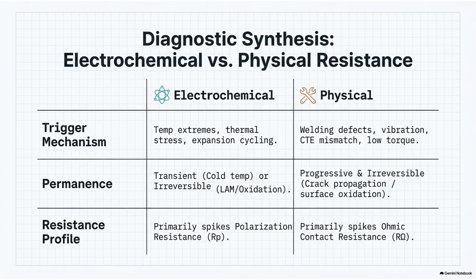Which introduces fretting wear and oxidation, right? Yes. Bare copper oxidizes very rapidly in the presence of humidity. And here's the critical electrical distinction we have to make. Copper oxide is a semiconductor bordering on being a total insulator. It blocks current. It is highly resistive. So as the bolt relaxes, a vibration causes microscopic rubbing, which we call fretting, between the bus bars. This fretting continually breaks off fresh copper particles, which immediately oxidize. Oh, so it just keeps building up more and more rust, basically. It builds up a thick, highly resistive crust of copper oxide directly inside the current path. And the contact resistance goes completely through the roof.